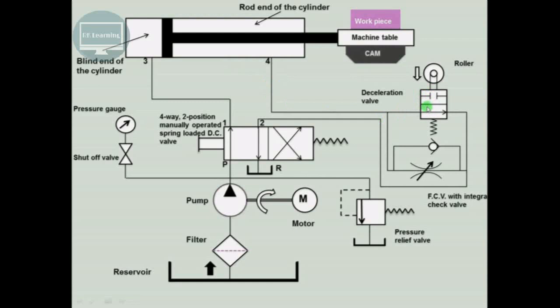This is the normally open type deceleration valve, connected in parallel with the flow control valve with integral check valve. At the end of the piston rod we have the machine table, on which the workpiece is mounted. At the bottom of the machine table there is a cam. During forward motion, the cam, machine table, and workpiece all move together in the forward direction. As soon as this cam touches the roller of the deceleration valve, it presses the roller downward and blocks the valve, giving the blocked position.